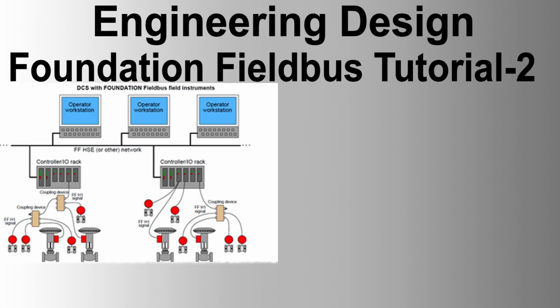Source/Sink model. The source sync model is designed to broadcast messages. It is one-to-many one-way communication without schedule. This model is sometimes called report distribution model. A source VCR transfers a message in the queue to an assigned global DLSAP address when the device has the token. Sink VCRs have the same global address and receive the same message from a source.